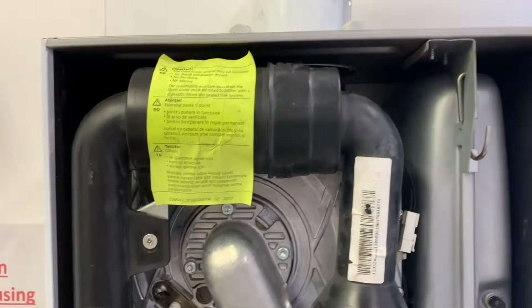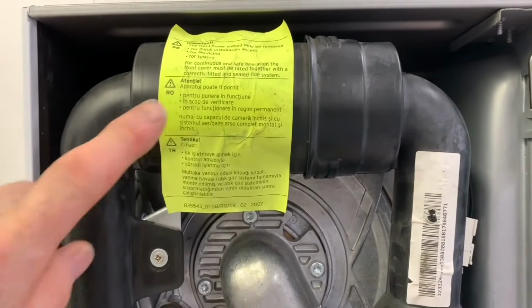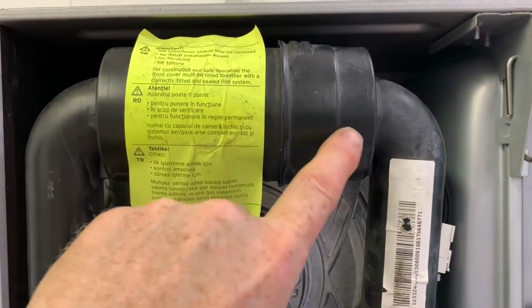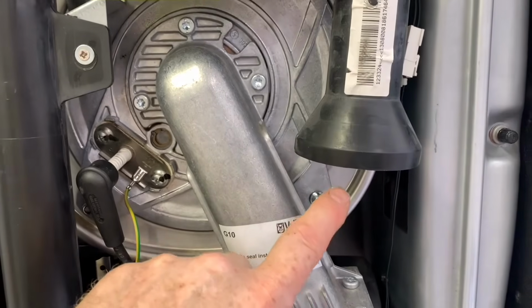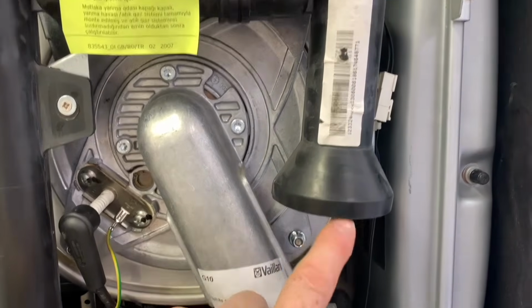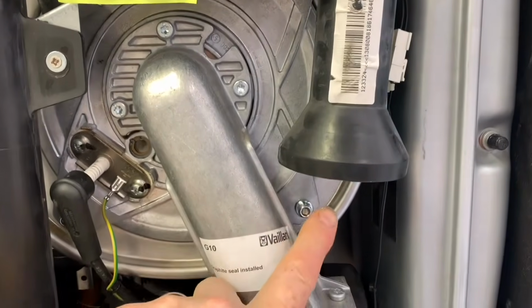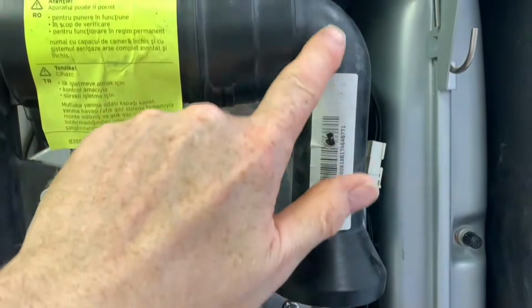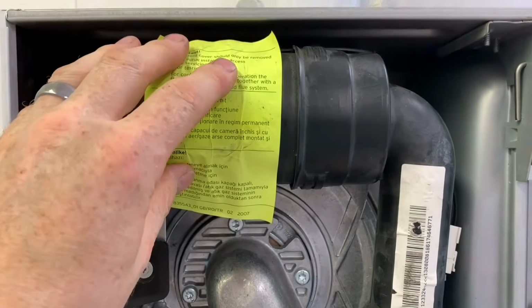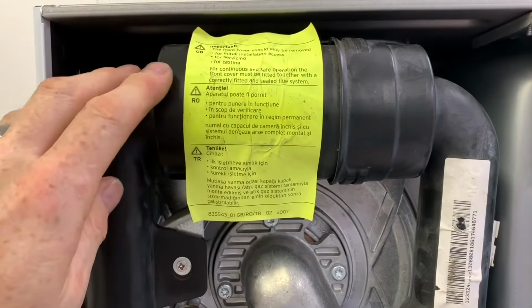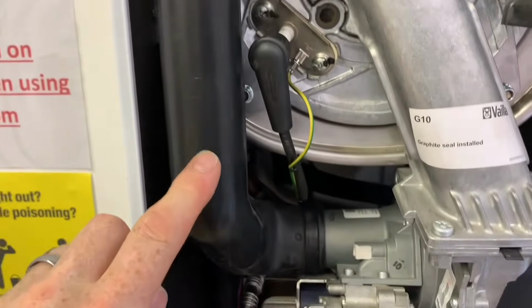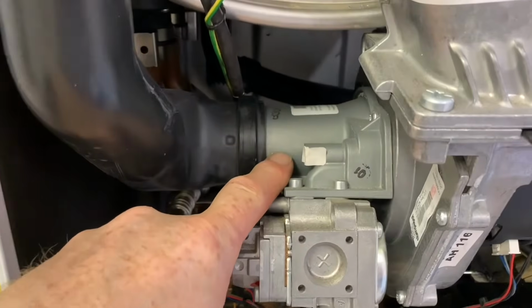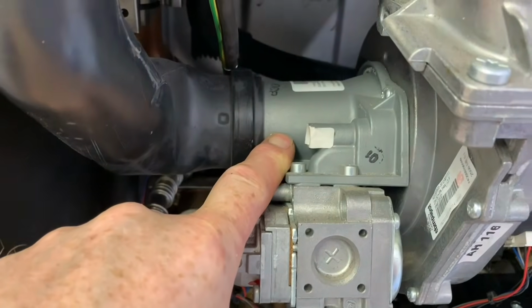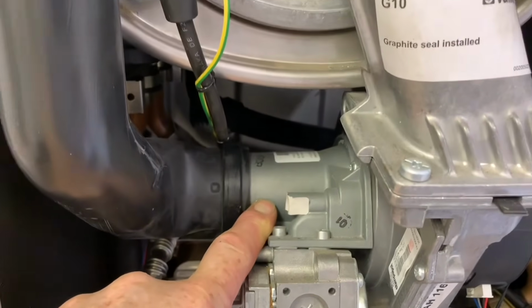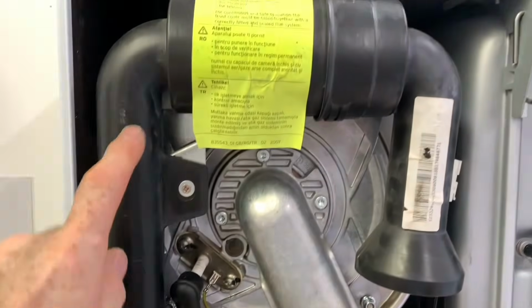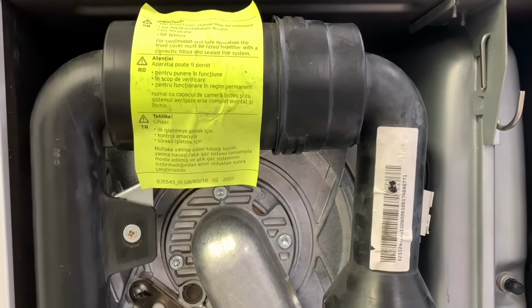Okay, now the first thing we can see is this black thing here. This is where the air for combustion comes in. This is a silencer. So air for combustion comes in here, it then goes along. This is a filter to filter out any bugs or anything like that. And then it goes down and into the back of the fan. So again, we'll have a look at that closely when we get it off. So the first thing you see is this silencer.